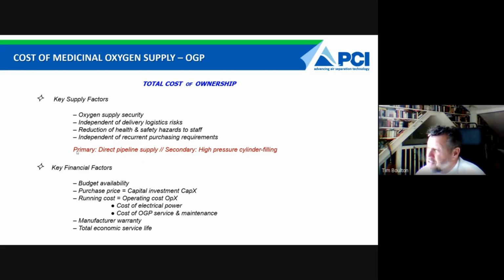Why? Because the systems will generate enough pressure in the pipeline, 3, 4, maybe 4.5 bar typically. You do not need more than that. If you take your oxygen and you put it into a high pressure booster, fill the cylinders, the oxygen is boosted to 150 to 200 bar pressure. You then take it to the patient and you then pressure it back down. You need a pressure reducer for it to be able to use in your ventilators or in your anesthesia machines. Cylinders are only necessary for logistics purposes, but it is very expensive to use a high pressure booster. A high pressure booster is expensive to buy. It can be almost as expensive as the actual oxygen generation plant itself.